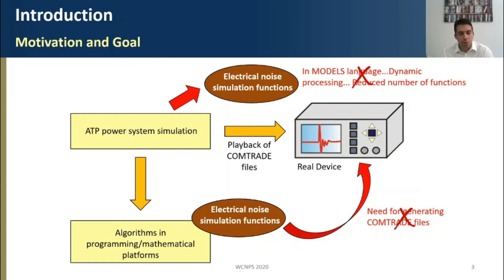The proposal in this paper consists of interacting the ATP with the MATLAB program, which is considered a good mathematical platform with promptly available functions that are capable of simulating electrical noise. Then we take these noise signals, import back into ATP environment, which is then responsible to generate COMTRADE files that can be used to test real devices. This is our main goal here.